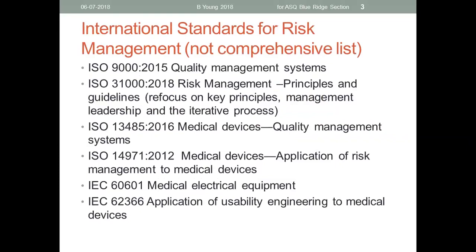IEC 60601 contains a lot of risk management requirements for medical electrical equipment, and then the IEC 62366 applies to the risk management of human factors or usability engineering for medical devices.